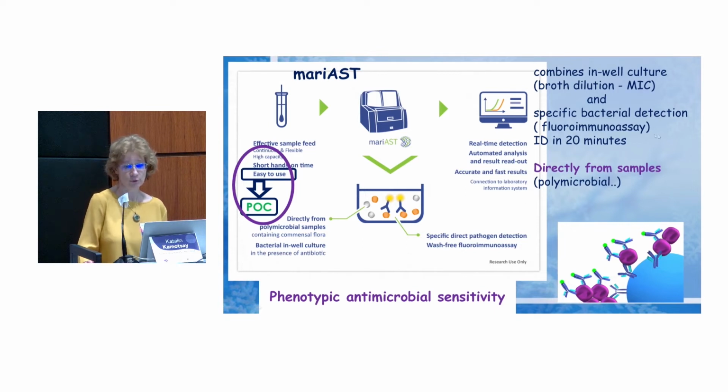It's a fluoroimmunoassay which makes an ID in 20 minutes, and also an MIC method, so antibiotic susceptibility testing too. So there is phenotypic antimicrobial susceptibility directly from the sample, even polymicrobial, and very easy to use, so it can be used as a point-of-care method.